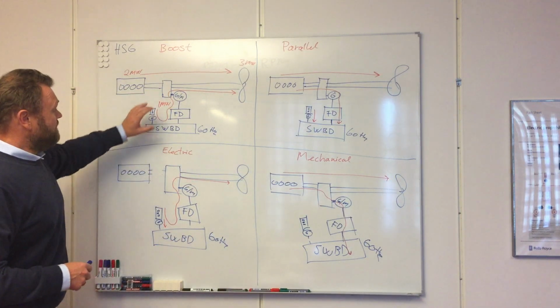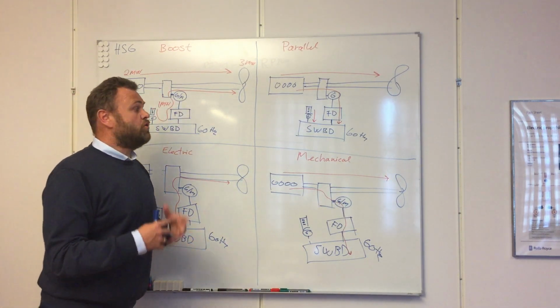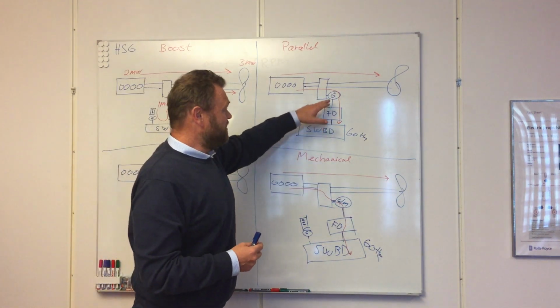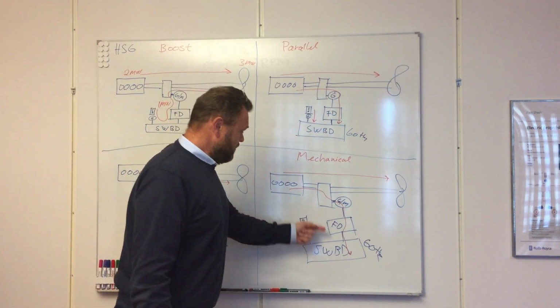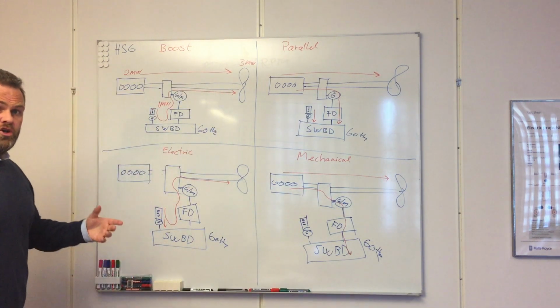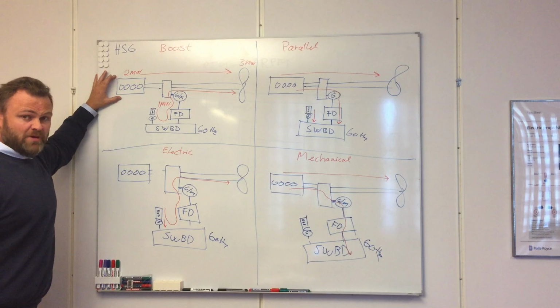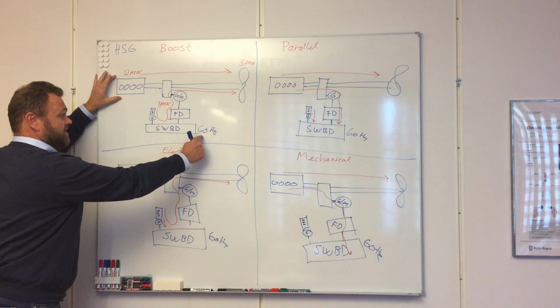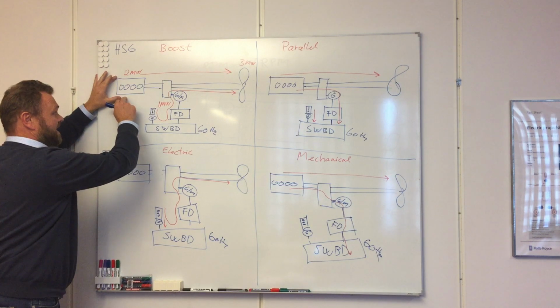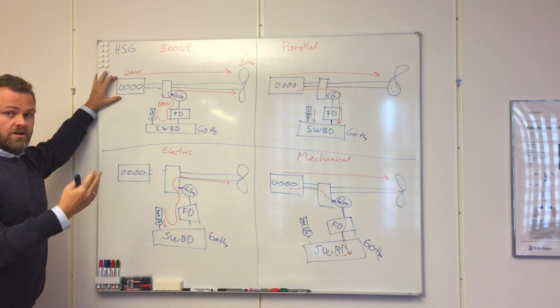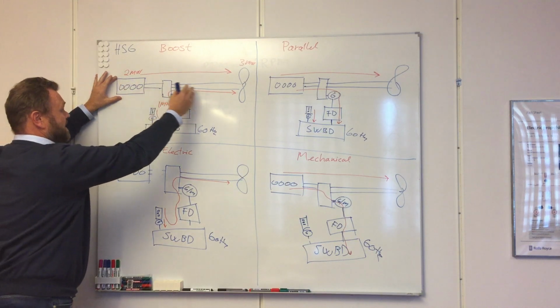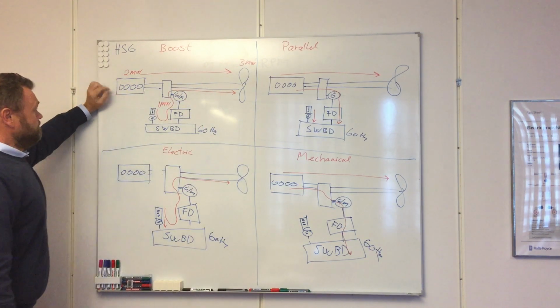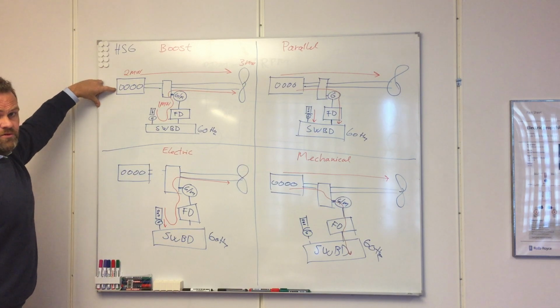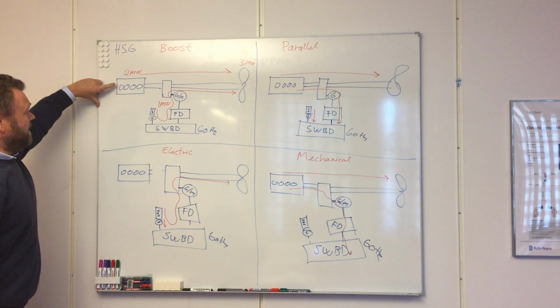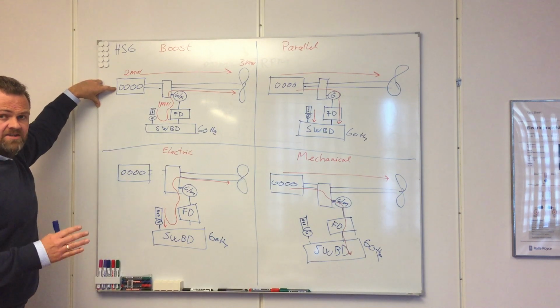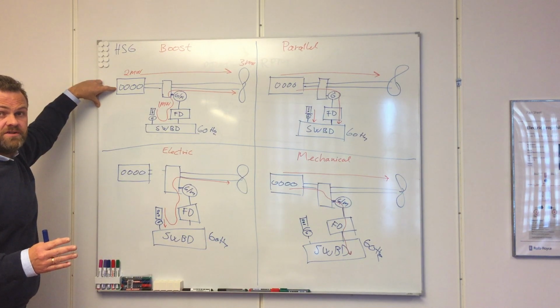When you have a frequency converter converting the frequency between the generator and the switchboard, in all these cases, you are suddenly not dependent on the frequency on the switchboard from the main engine. In this case, you may have a motor, and you don't have to pick an engine prepared for 50 or 60 hertz.